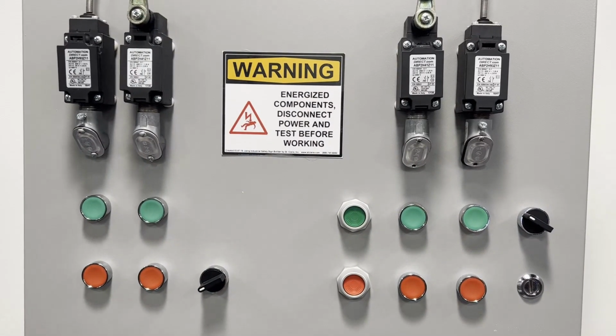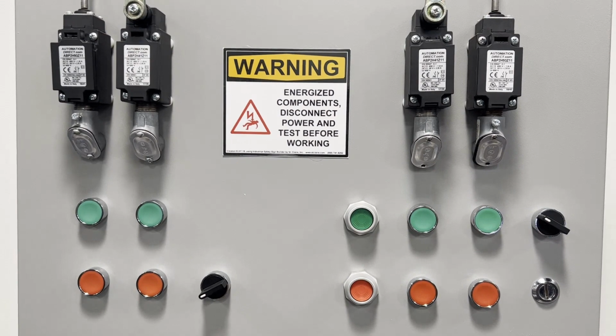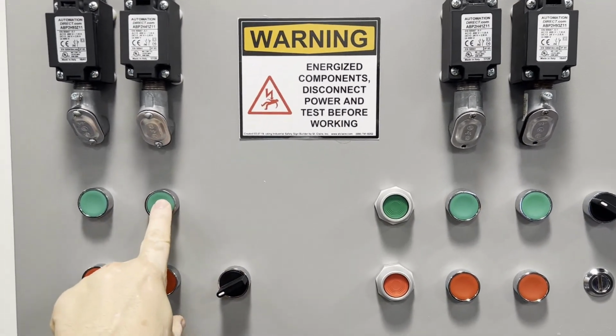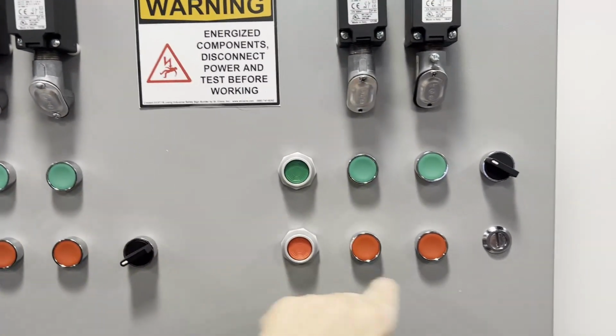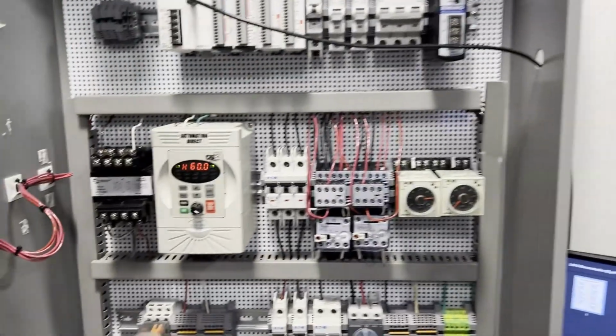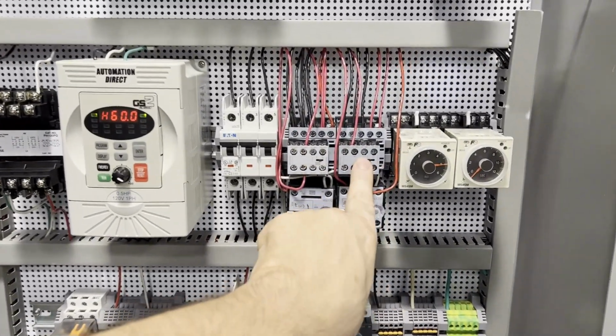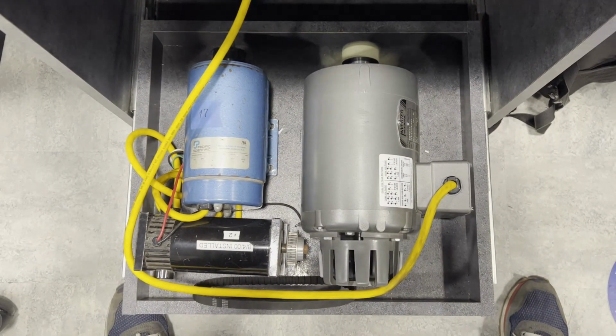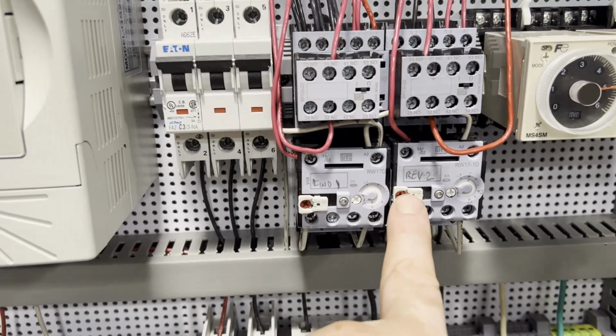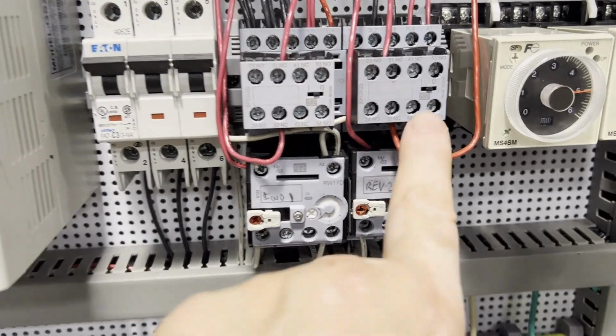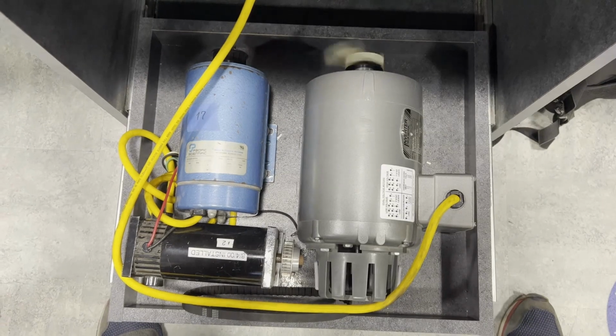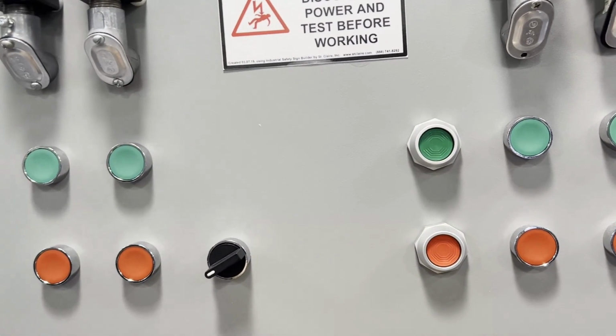Test number 4, reverse overload. Start out pushing the reverse button. Hear the reverse contactor. Verify reverse contactor closed. Motor rotating in reverse direction. Reverse overload. Reverse contactor opens. Motor coasting down in reverse direction. That concludes our reverse overload test.